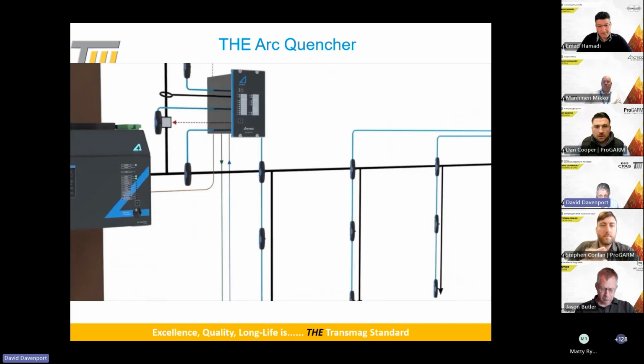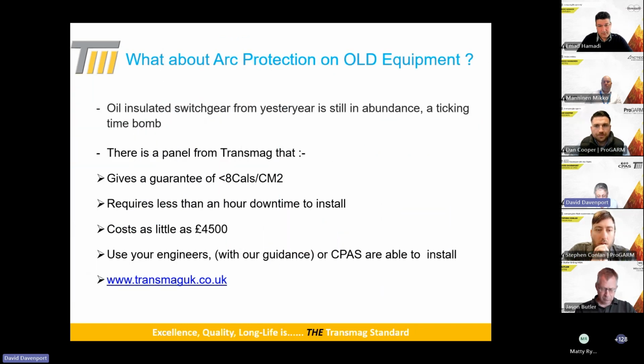Yeah, this is a typical arc quencher. The sound's been taken off really from a marketing point of view - it's not about marketing a particular type of quencher. That one is the Arcteq arc quencher, which we market because it's resettable and reduces the calorie level down to around 1.2 calories per centimetre square. But there are other suppression systems available - it can do a suppressant type, and Siemens also make an arc flash quencher in partnership with Arcteq. So there are other types about as well, and they all do a very similar job.